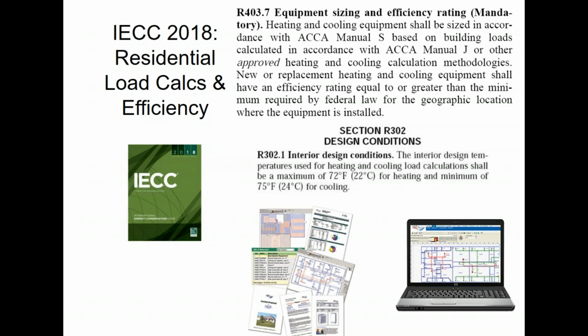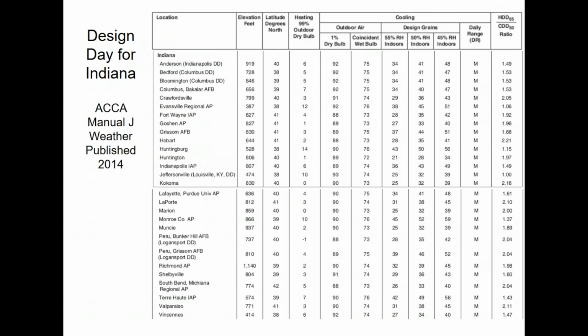In any case, the code requires you to do the load calc. It requires you to load calc with these temperatures that we have specified here for indoor design conditions. It also has requirements for the outdoor design conditions. It refers you to using the ACCA Manual J weather. So this is out of the 2014 ACCA Manual J weather document. These are all of the weather stations for Indiana that we're talking about specifically. I highlighted South Bend just so we can have an example here.